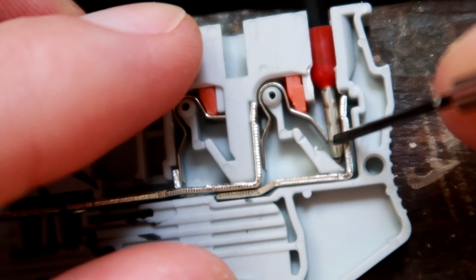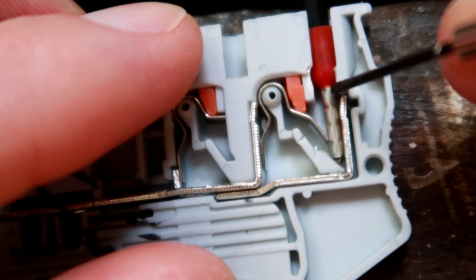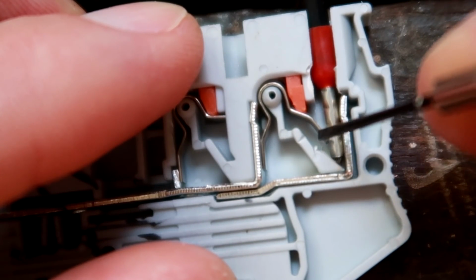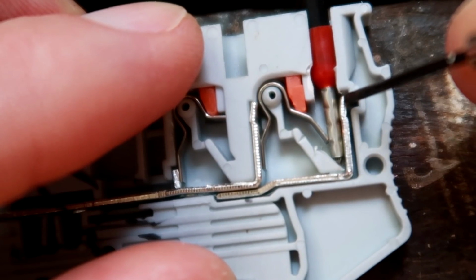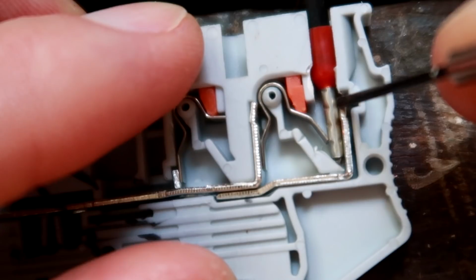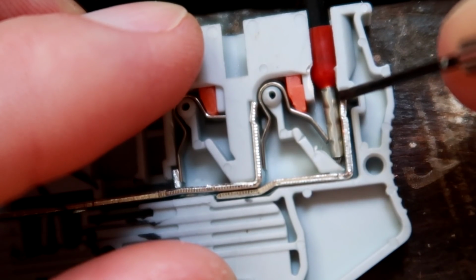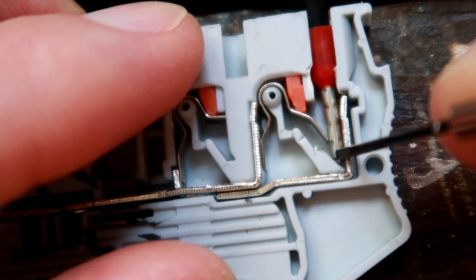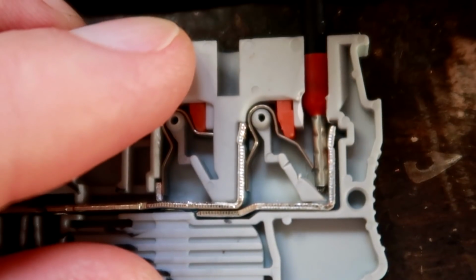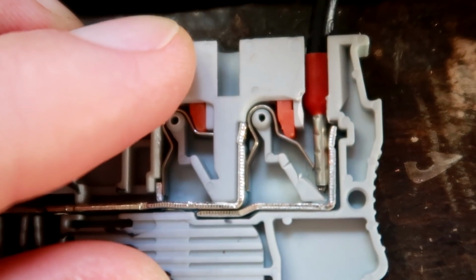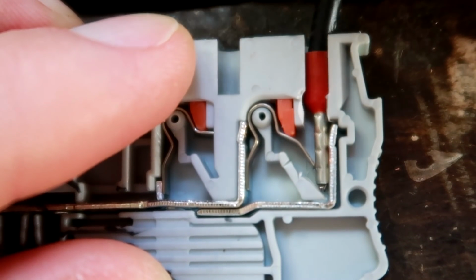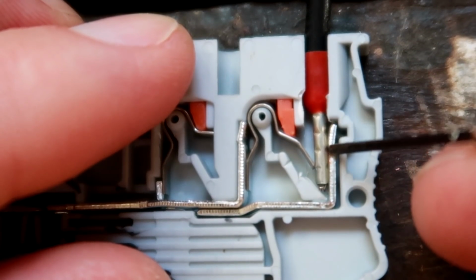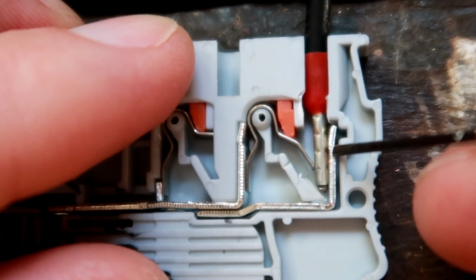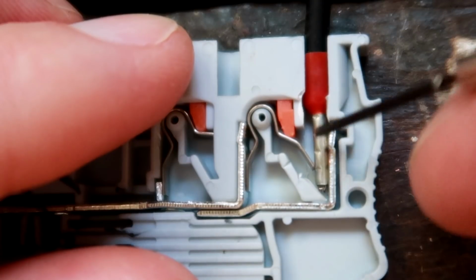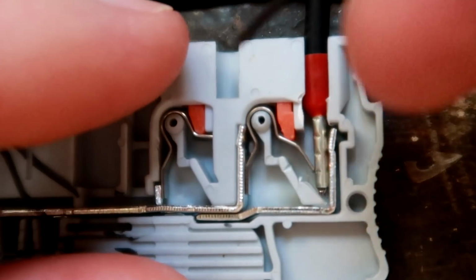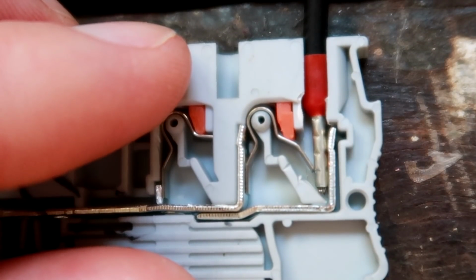And here you can see the ferrule is much tougher than just a single copper cable and stays straight. The spring presses the whole ferrule against the bus bar, and we've got the contact area starting from the top of the bus bar all the way down to the end of the ferrule. Even if we move the cable around, it stays connected perfectly fine to the bus bar. So we get a much larger contact area from the cable to the bus bar with a ferrule, and that's why I prefer using ferrules even in these clamping terminals.